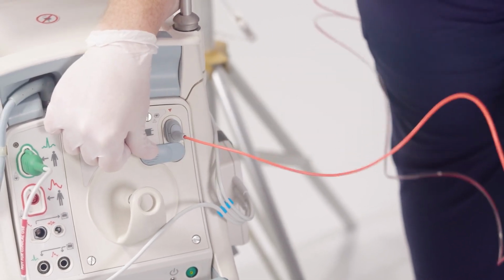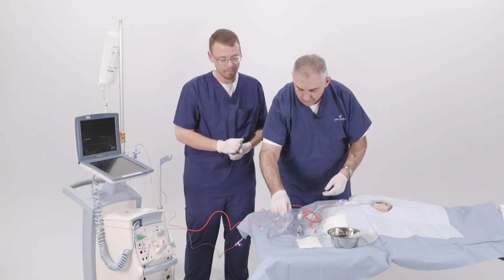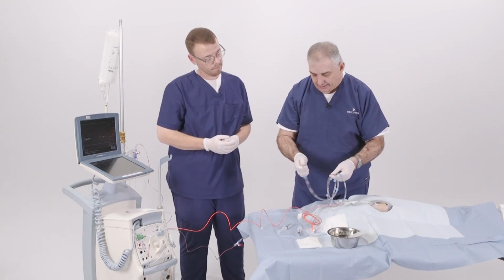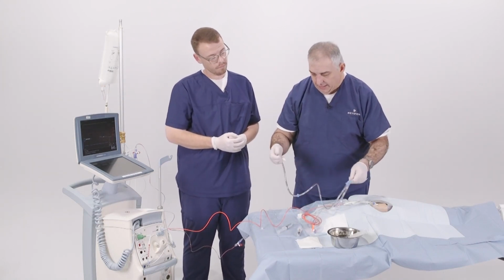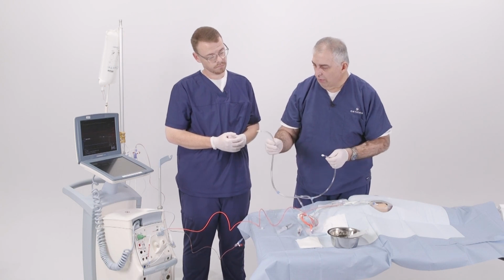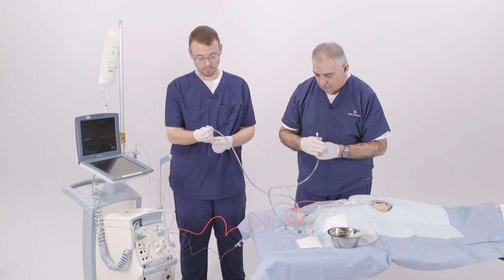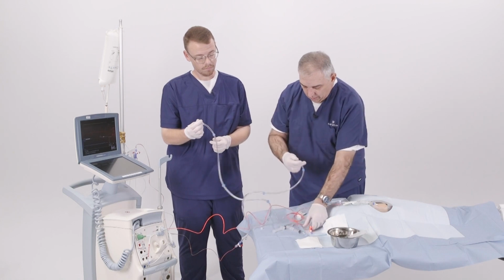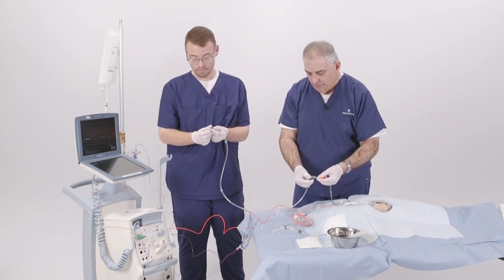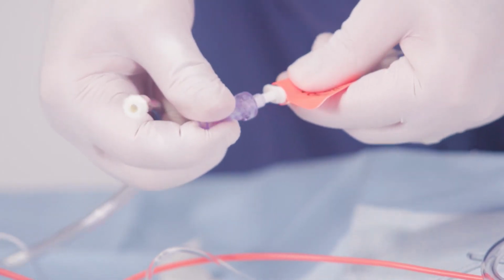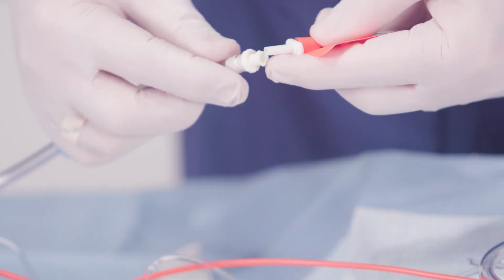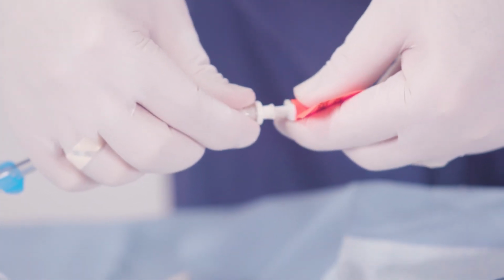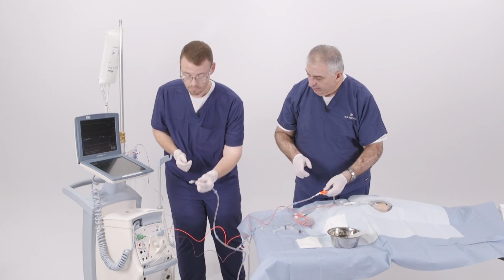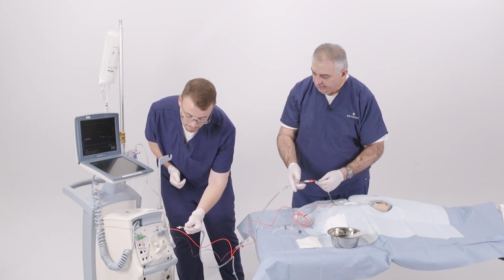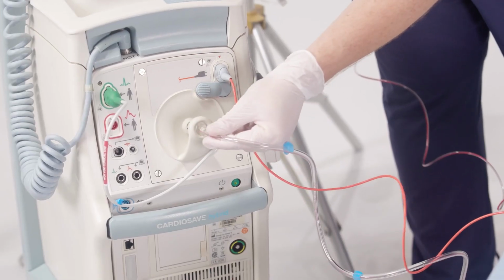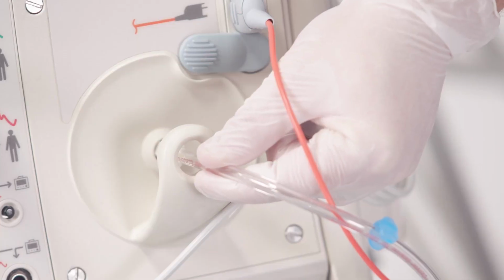Excellent. The last thing we need to do is I need to take the extension tubing. I need to hand the male lower end to you. Now it's safe to take the 1-way valve off of the extracorporeal tubing, and I'm going to attach that. And now if you can insert the male end of the extension tubing into the patient interface module.